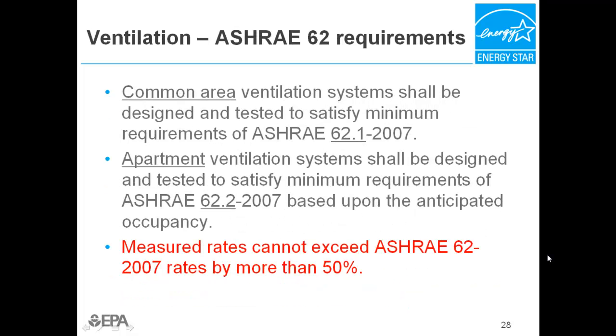Identical to the prerequisite in the performance path, common area ventilation systems shall be designed and tested to satisfy minimum requirements of ASHRAE 62.1, 2007, and apartment ventilation systems shall be designed and tested to satisfy minimum requirements of ASHRAE 62.2, 2007. Providing dedicated outdoor air to each unit is still recommended, but not required. Kitchen exhaust must still be vented to the exterior. The additional requirement of the prescriptive path is that the measured rates cannot exceed ASHRAE by more than 50%.